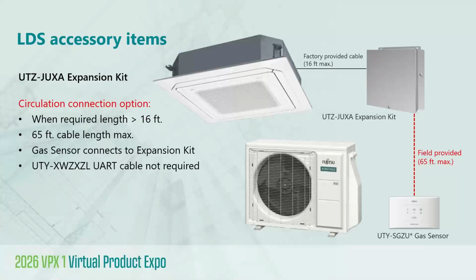So earlier we covered that the gas sensor connects directly to the indoor unit for circulation as mitigation, with the ever important note that, again, that UART cable is limited to 16 feet, which, by the way, in case you're wondering, cannot be extended in the field. That's just a function of the communication power circuitry. So if and when the wiring distance exceeds 16 feet between the gas sensor and the indoor unit, an option you have here is the UTZ-JUXA, otherwise known as the expansion kit, that can be used to connect the gas sensor instead. So as you see in this configuration, off to the right with the dashed line, a field-provided cable, minimum 3 conductors, now allows up to 65 feet, so pretty generous, to the gas sensor.